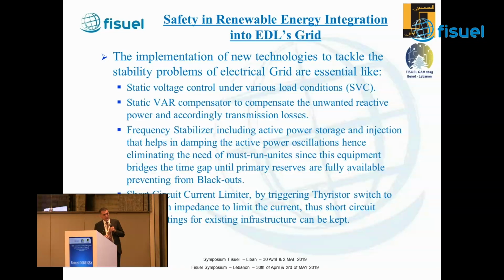Short-circuit current limiters, by triggering a thyristor switch to insert high impedance to limit the currents, allow the short-circuit current ratings of the existing infrastructure to be kept.